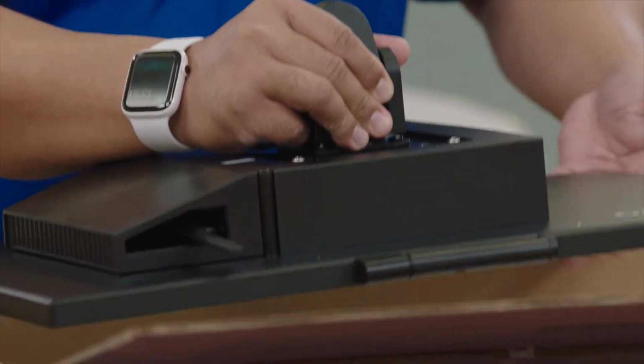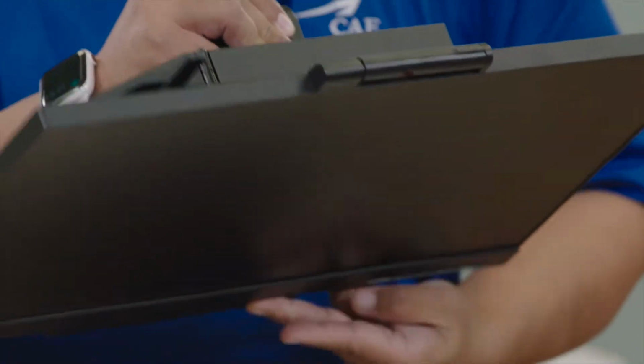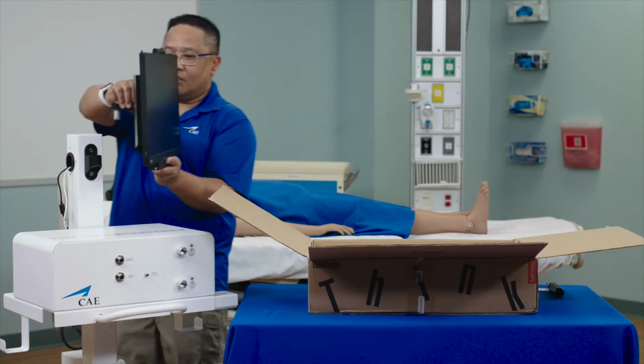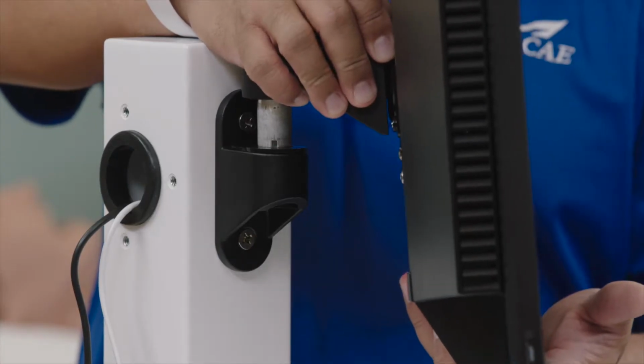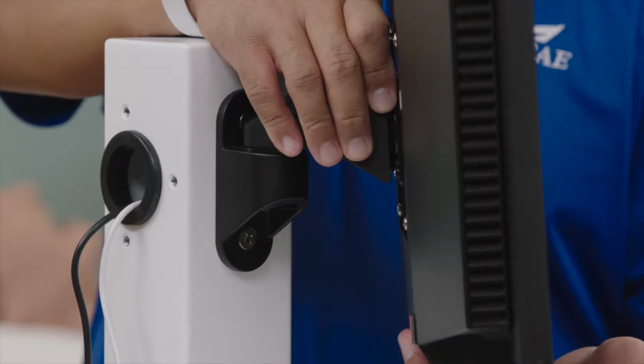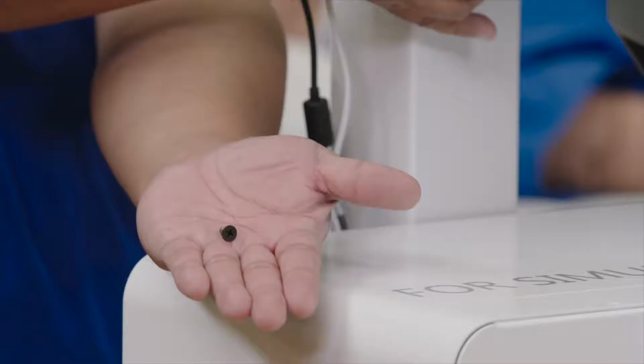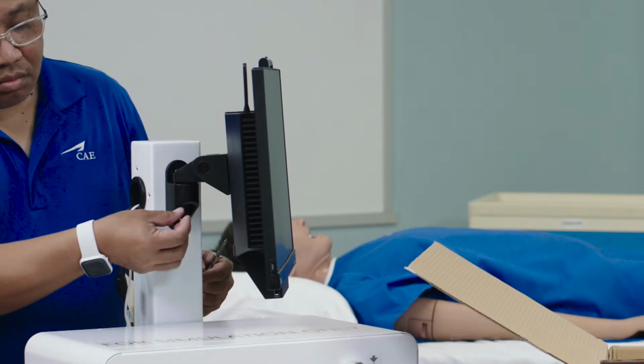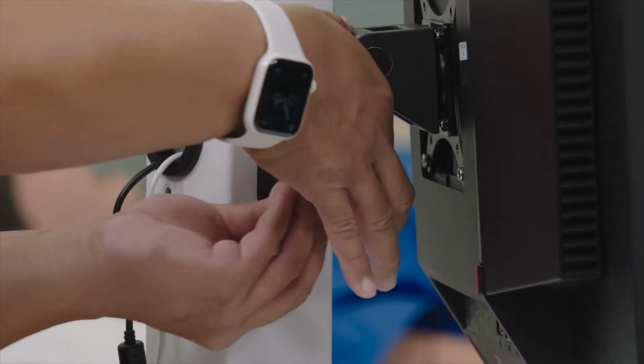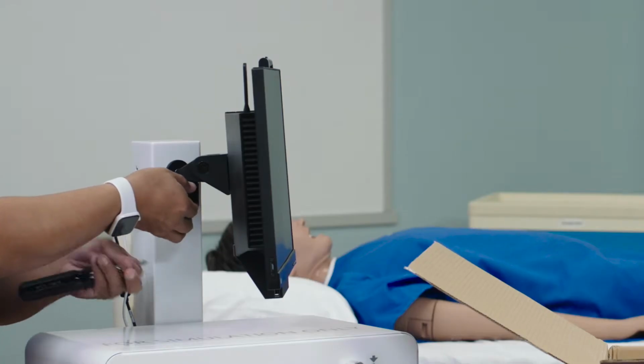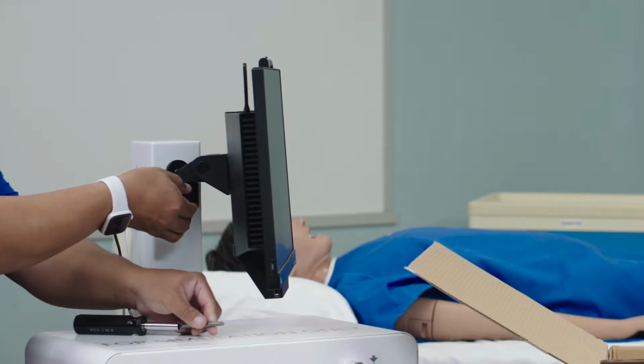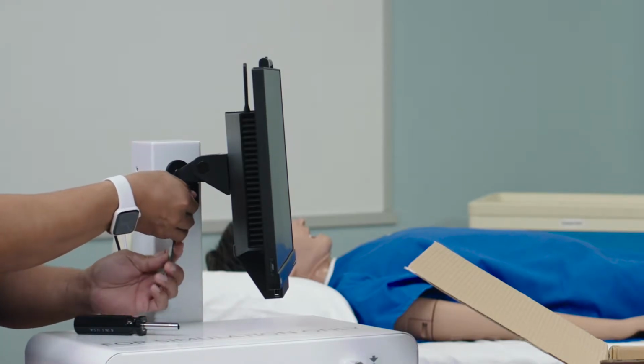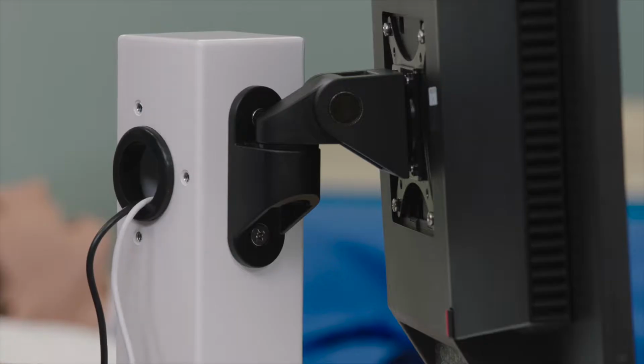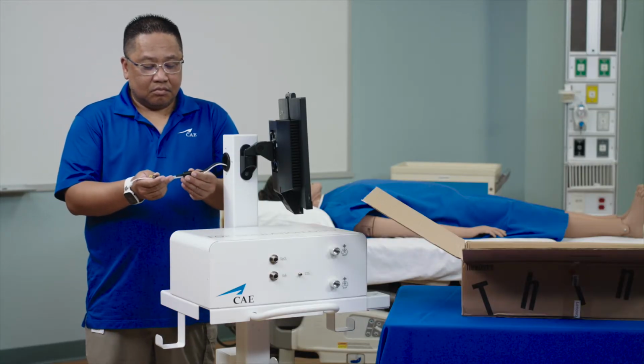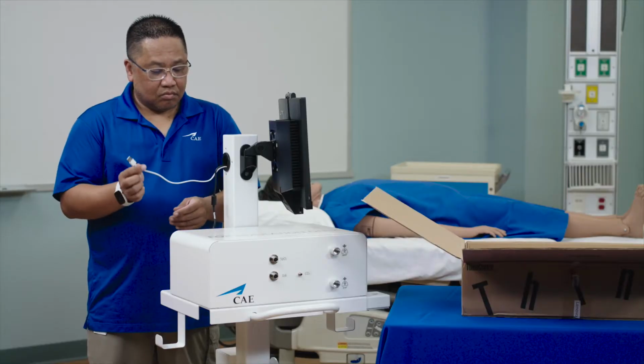Carefully lift the monitor from the styrofoam packaging in the box. Insert the VESA mount bracket knob onto the vertical support column of the medical cart. Place the additional washer and then the screw under the VESA mount bracket attached to the vertical support column. Take the attachment out of the screwdriver or use a short screwdriver to tighten the screw. Tighten the screw.